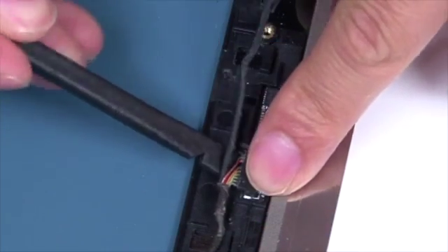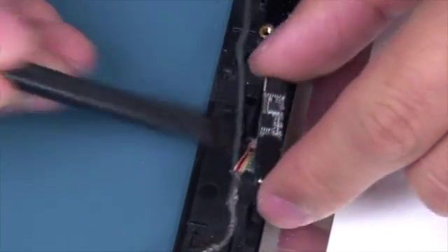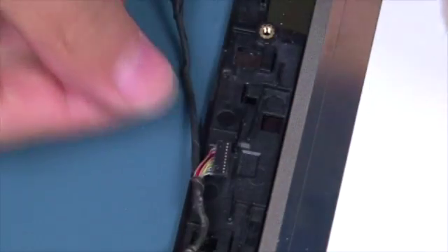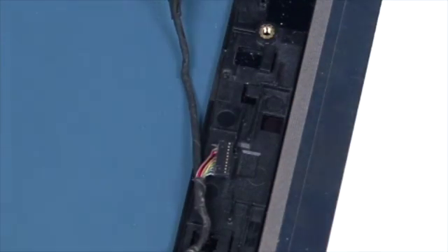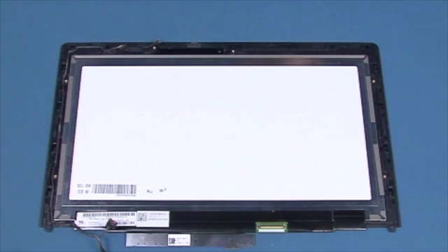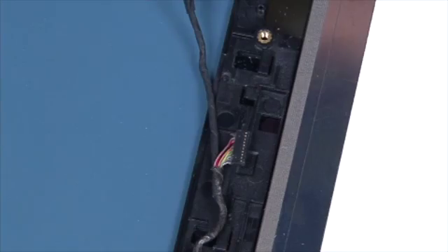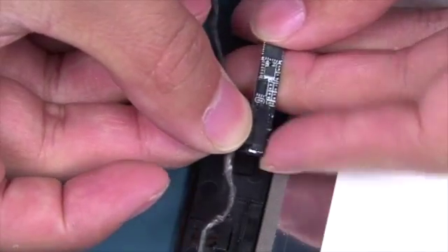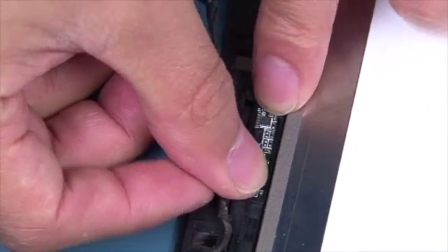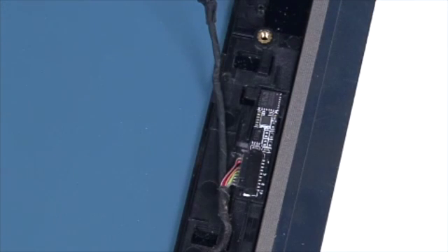Using a flathead probe, peel off the ambient light sensor from the top LCD panel. Disconnect the signal cable and remove the module. Reconnect the signal cable to the camera. Place the ambient light sensor back into position and press until it is properly taped.